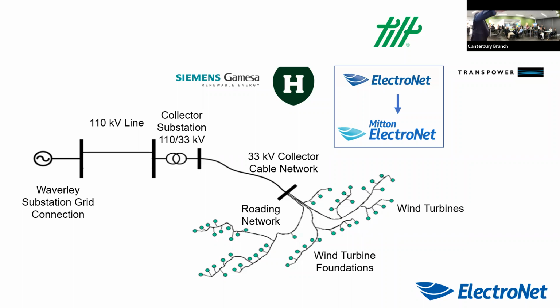So we went from the 110 kV line termination at Waverley substation. We designed and built the 110 kV line. We designed and built the collector substation, which steps down from 110 to 33 kV. Then we designed and built the 33 kV collector network, which runs from the 33 kV switchboard in the collector substation, with cables running to the switchgear in each of the wind turbines.